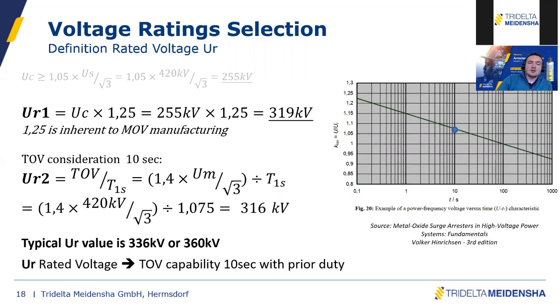So basically this is the ratio between the capability to withstand an overvoltage for 10 seconds and the capability to withstand a continuous power frequency voltage over its service life, so for 30 years. And this performance is more or less the same for most zinc oxide varistors. So if you want to make a quick calculation, it's quite common to use 1.25. So UC times 1.25 gives you the minimum rated voltage.